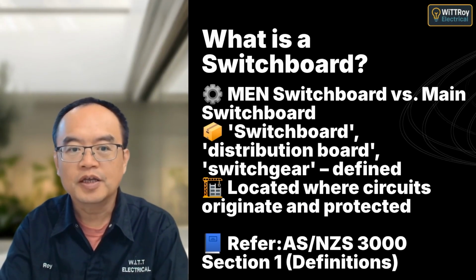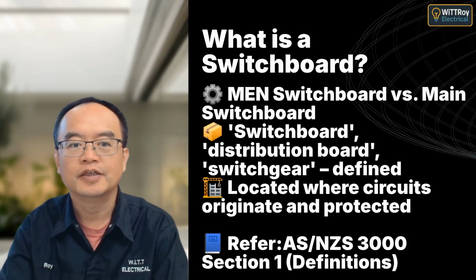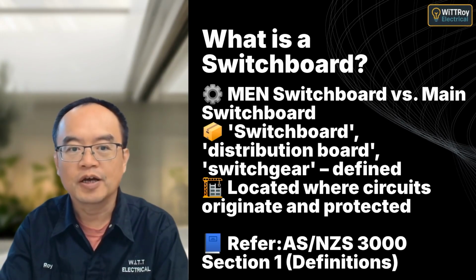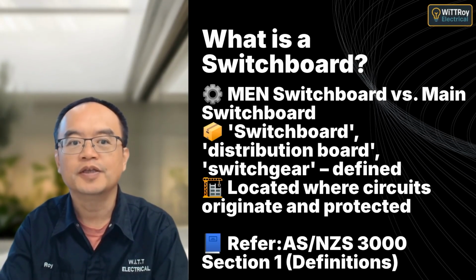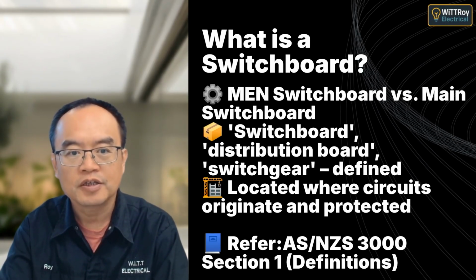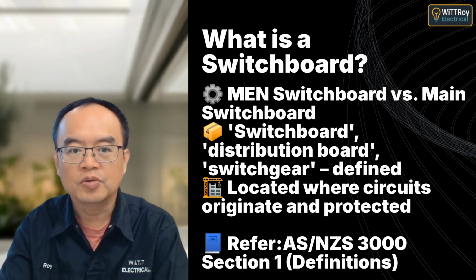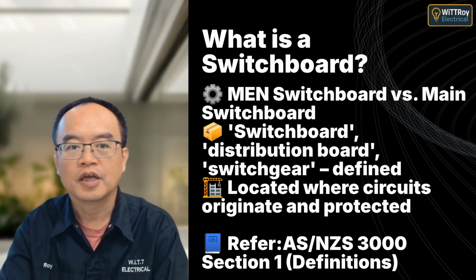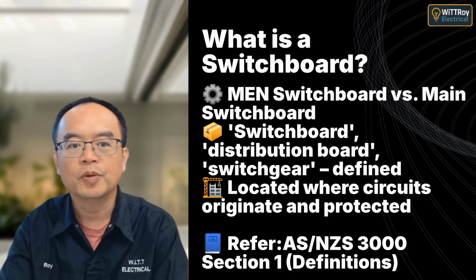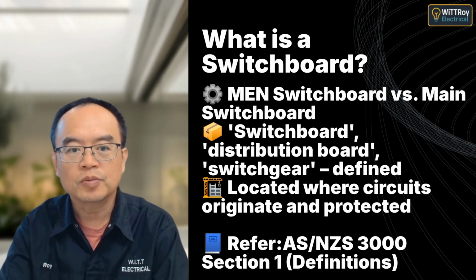A switchboard is where electrical circuits are controlled and protected. Under AS-NZS 3000 Section 1, an MEN switchboard is part of the earthing system, ensuring safety through neutral connections to earth. It's important to know the role of each component, switchgear, distribution boards, and main boards, in a complete installation.